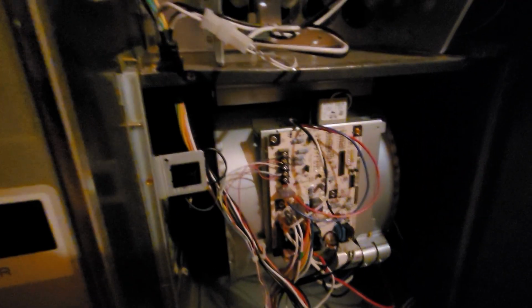If that wire is removed, neither the heating or the air conditioning can work. So what we have to do is control that wire in order to control the heating or the air conditioning on Shabbos. And next I'm going to show you how we did that. Now if you look over here, what I've done is I've removed the red wire for the transformer, and I ran a new wire over here, a 2-conductor bell wire. One terminal goes to the screw where the red wire previously went, and the red wire is spliced to the other terminal on this bell wire over here.